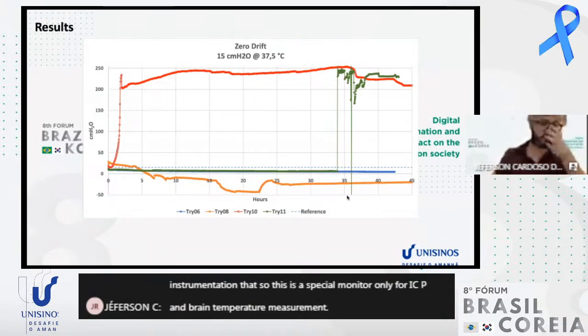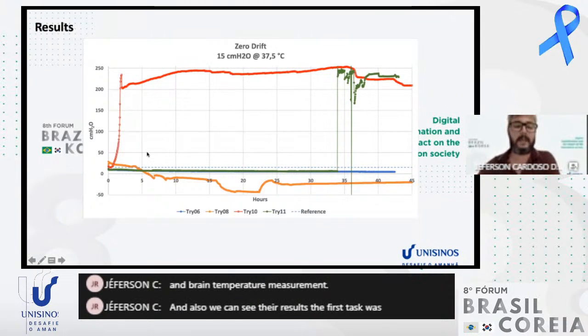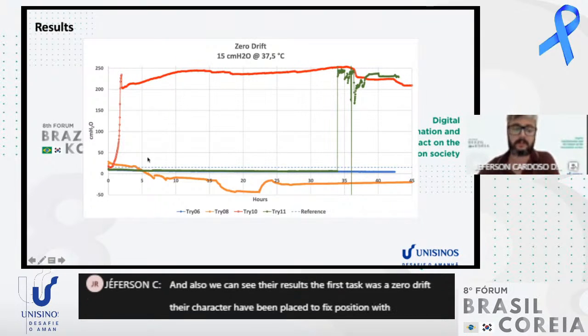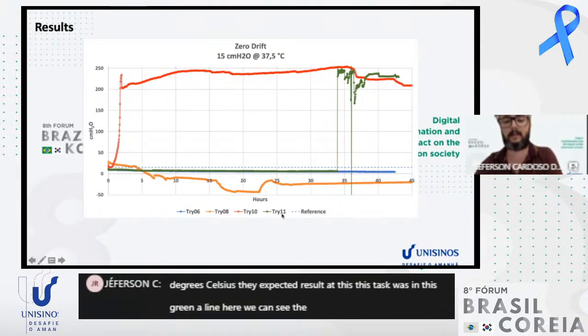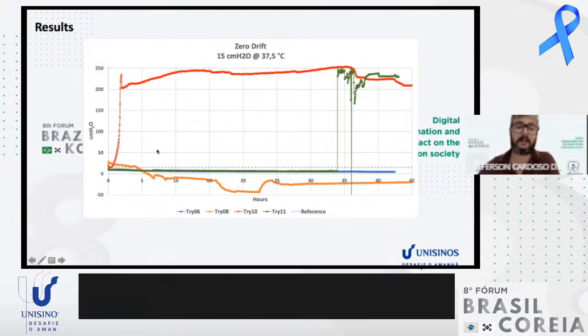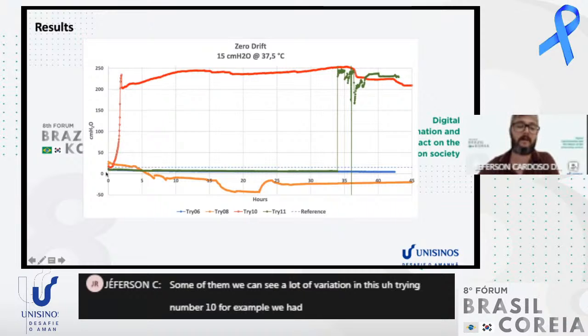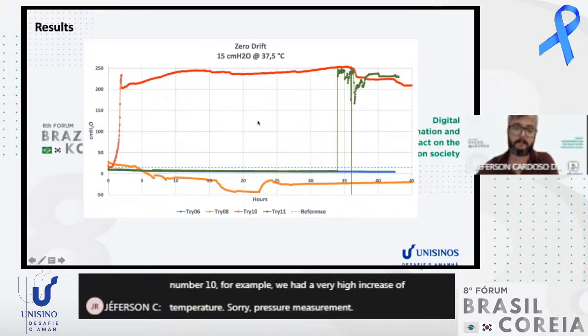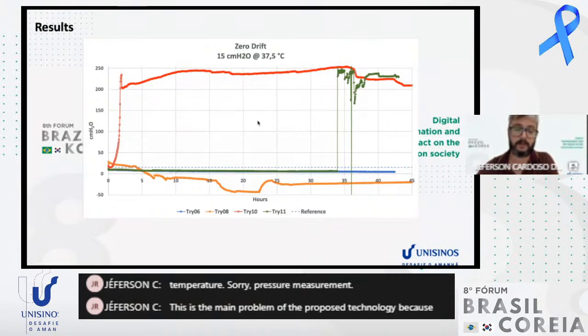And also we can see the results. The first test was the zero drift. The catheter was placed in a fixed position at 15 centimeters of water, with a constant temperature of 37.5 degrees Celsius. The expected result for this test was this green line here. We can see prototype number 11, showing a constant pressure measurement along the time. Some of them show a lot of variation, like in this try number 10, for example, where we had a very high increase of temperature and pressure measurement. This is the main problem of the proposed technology, because we're using a plastic tip.